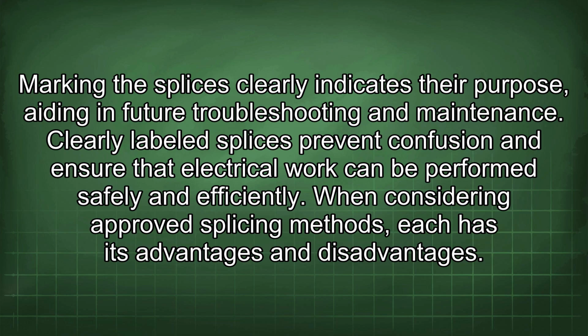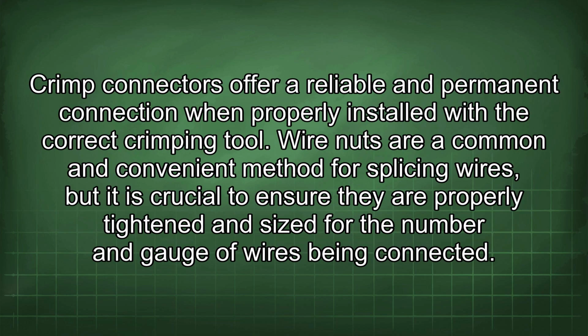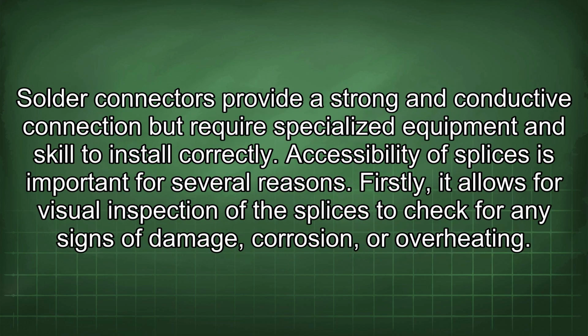When considering approved splicing methods, each has its advantages and disadvantages. Crimp connectors offer a reliable and permanent connection when properly installed with the correct crimping tool. Wire nuts are a common and convenient method for splicing wires, but it is crucial to ensure they are properly tightened and sized for the number and gauge of wires being connected. Solder connectors provide a strong and conductive connection, but require specialized equipment and skill to install correctly.